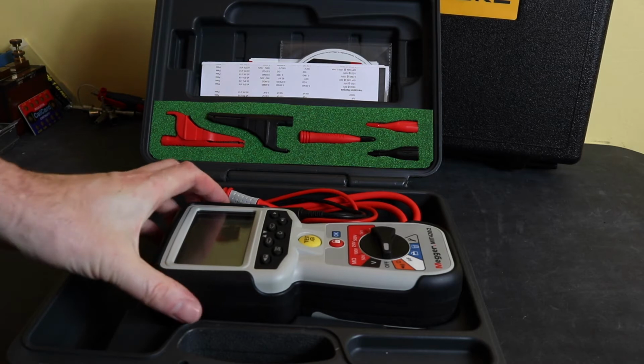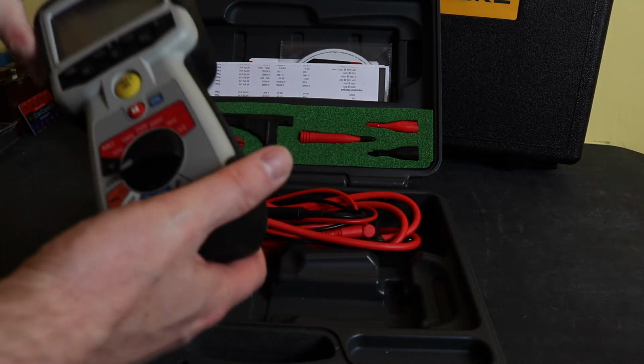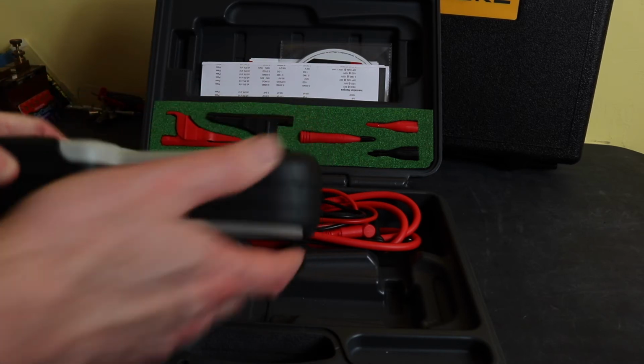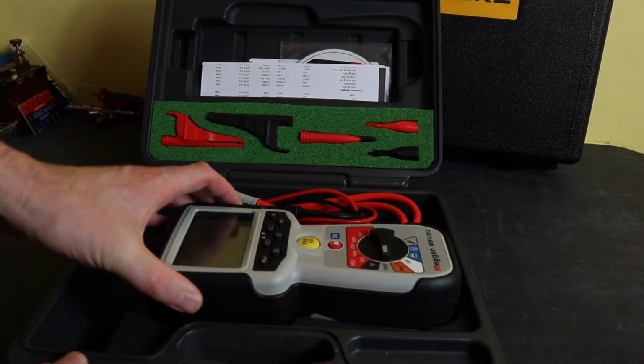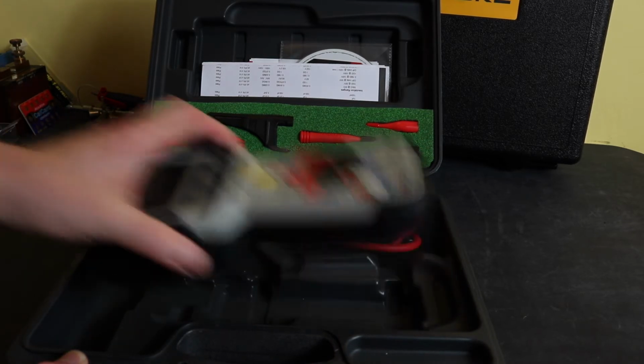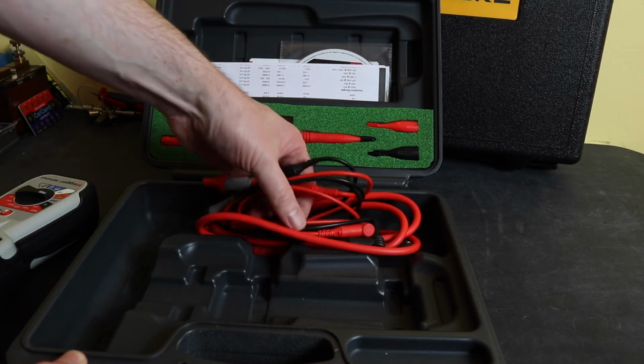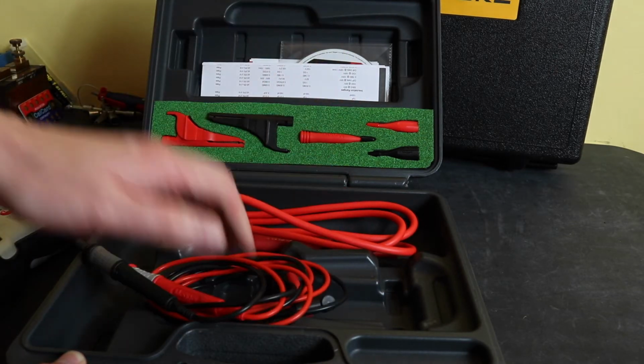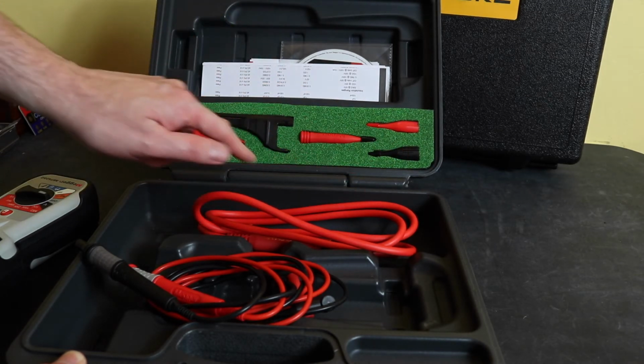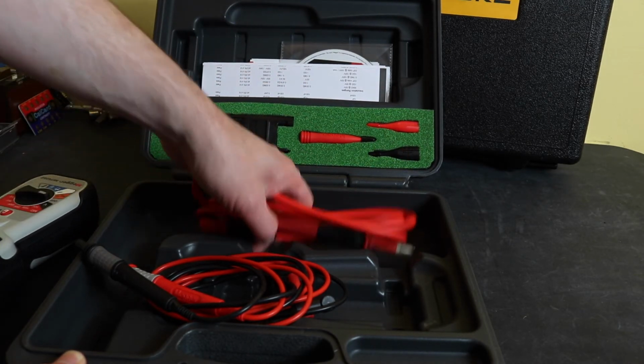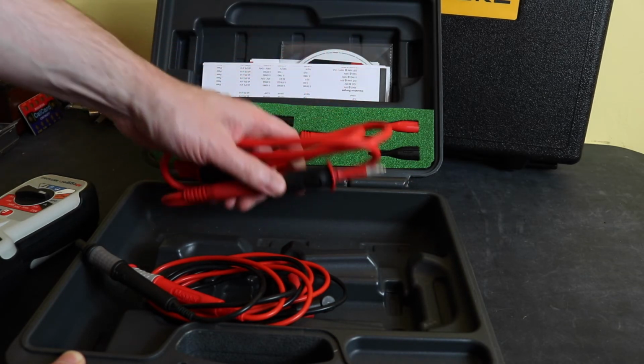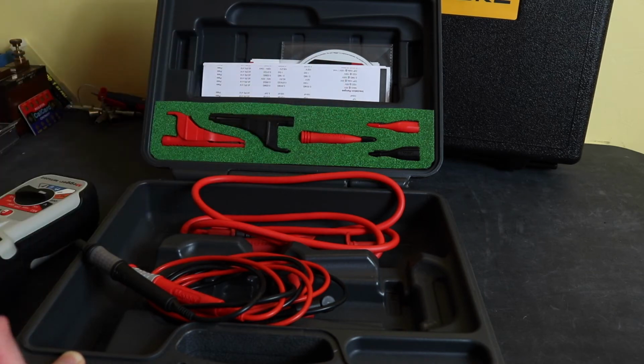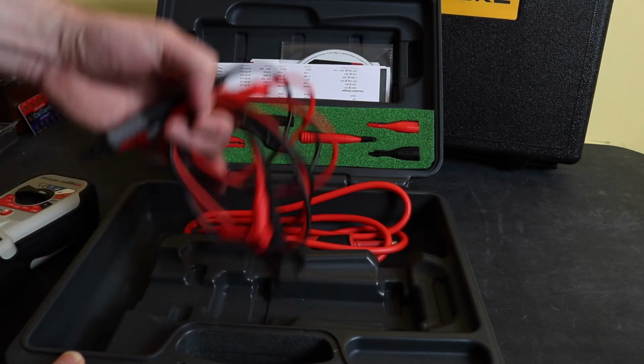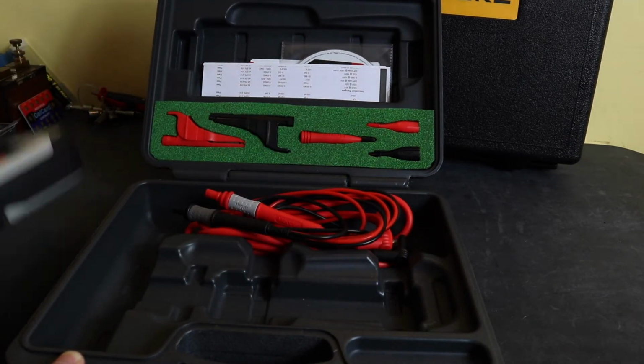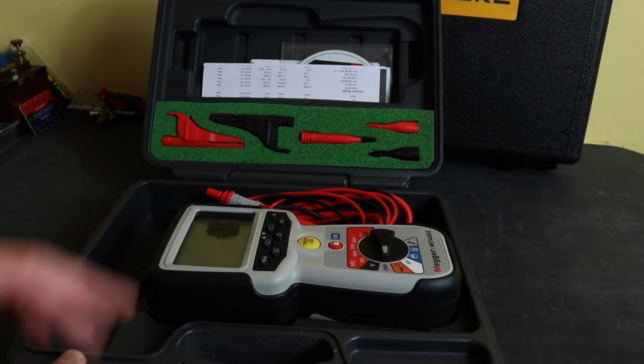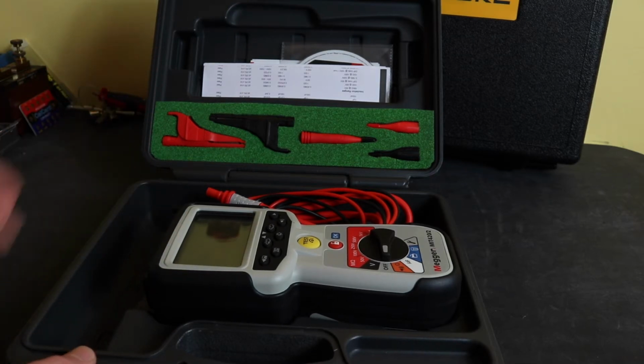The Megger MIT-420, again, has a blow moulded case to house everything in. This one is shaped a little bit better, and the meter actually sits in quite solidly in a little cutout there. Alongside that, you again get a set of silicon test leads with some short probe tips, a set of croc clips, and a remote probe that has an extended probe tip should you require it, and that's pretty much all you get in that. There's no thermocouple with this instrument because it doesn't have the ability to measure temperature.